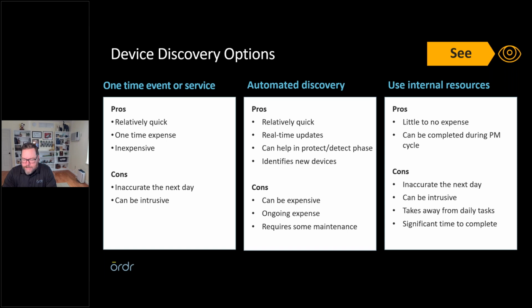One of the downfalls for this process, though, is that it's inaccurate the next day. So that one day you come in, you collect your information, the next day GE comes in, Philips comes in behind you and upgrades that software version on that device, and your information is no longer accurate. If you're using DHCP, which is becoming more and more commonplace with fleet medical devices, where it wasn't years ago, that IP address is only good for a certain length of time, and it's going to refresh and get a new IP address, so that can't accurately be captured. And even though they're very good at what they do, this is intrusive. You're taking the piece of equipment down, and you're taking it down maybe within service hours or in the evening, and you're taking away from time that device can be used, or being intrusive by going into patient rooms.